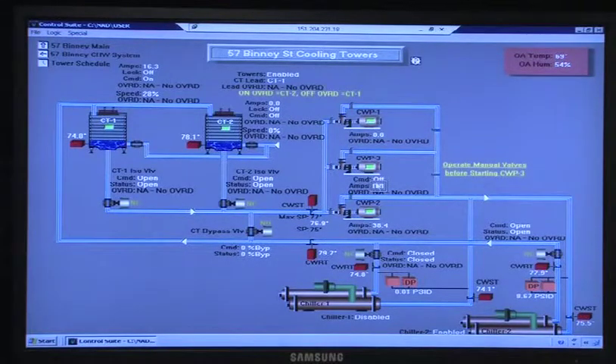Okay? It's a valve operation. Automation wise, you can command it on. Valving, you gotta valve it off. It's not automated. So then discharge out of the pumps, come down, and it feeds chiller 2 condensing water or chiller 1 condensing water. Alright?